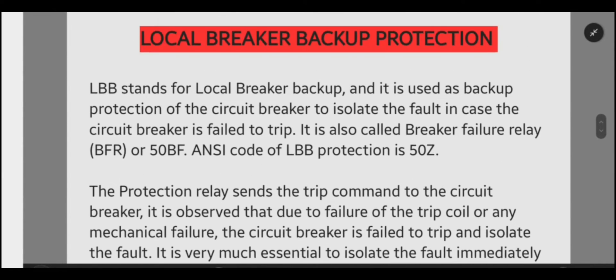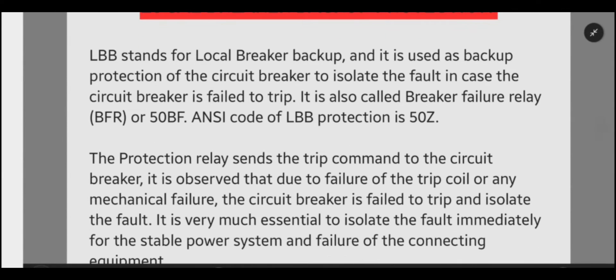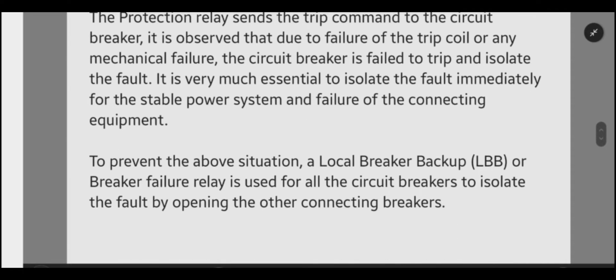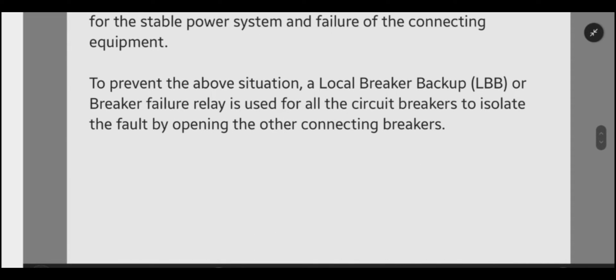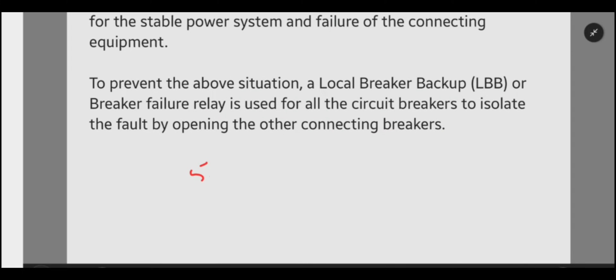If any fault occurs in the transmission line — suppose a distance fault happens — and due to any reason like mechanical failure or electrical failure of the breaker, the breaker associated with the fault fails to trip, then the LBB backup protection initiates. This LBB protection is also written in the relay as 50Z or 50BF, that is breaker failure relay.